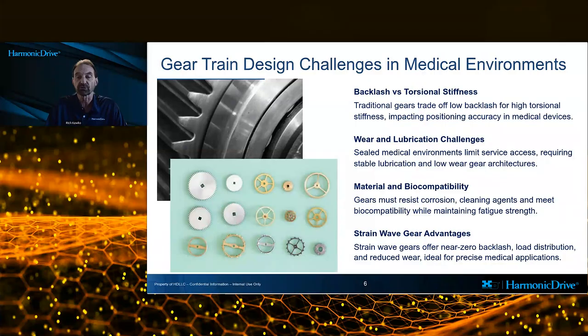Preloading techniques can reduce backlash, but they often increase friction, wear, and sensitivity to manufacturing tolerances. Wear and lubrication present another major challenge, particularly in sealed or sterile environments. Medical systems may operate for years without service access, meaning that lubricant breakdown or contamination can directly limit system life. This drives the need for gear architectures with low sliding contact and stable lubrication behavior.